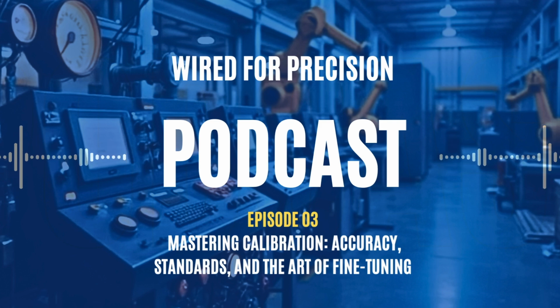5. Respect the environment. Avoid calibrating instruments in unstable or extreme conditions unless necessary. Vibrations, temperature swings, or moisture can introduce errors. 6. Ensure safety. For hazardous locations, use intrinsically safe or ATEX certified equipment. Always follow lockout tagout procedures and PPE protocols. A well-calibrated system is not only accurate, it's also auditable and safe. And if you ever get audited, your documentation and procedures speak louder than words.